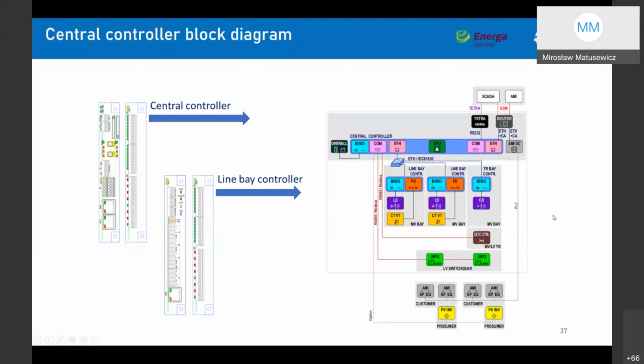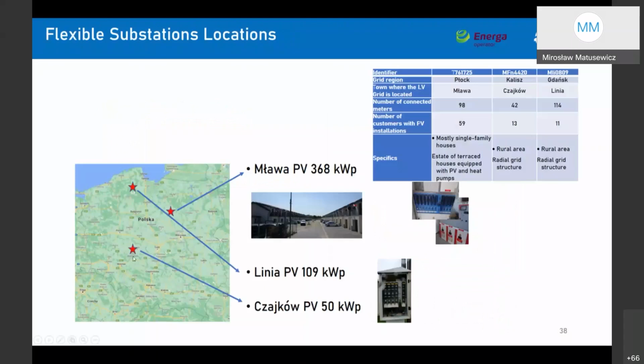So where can we locate our flex station? The pole flex station will be located in rural areas of Wejherowo and Ostrów Wielkopolski, under the Gdańsk division branch and Kalisz branch of our company. The indoor flex station will be located in Mława, which is a very important and special place, because it's an estate of terraced houses, as we can see in the photo. Every house is equipped with photovoltaic and a heat pump, so there is almost 400 kilowatts on this one street, a big concentration that causes a lot of problems. This is the first and most important step for our problem, and we try to address it this way.